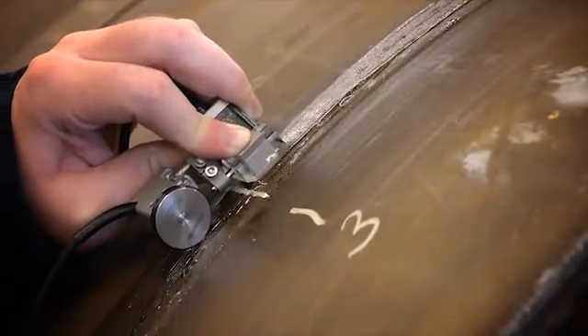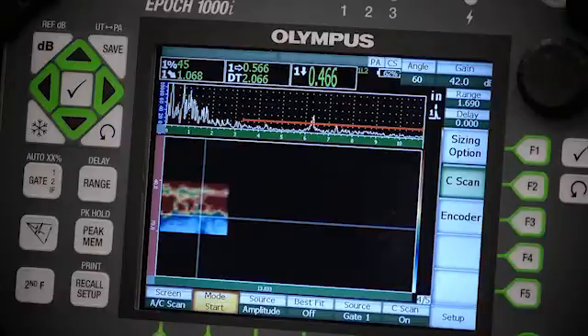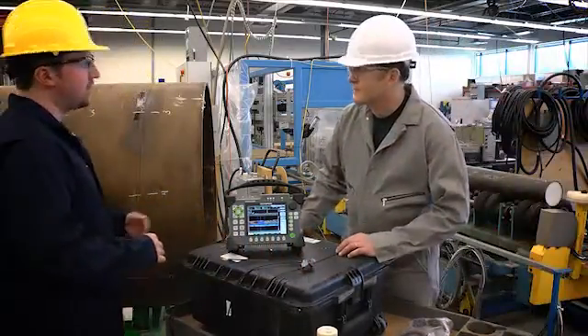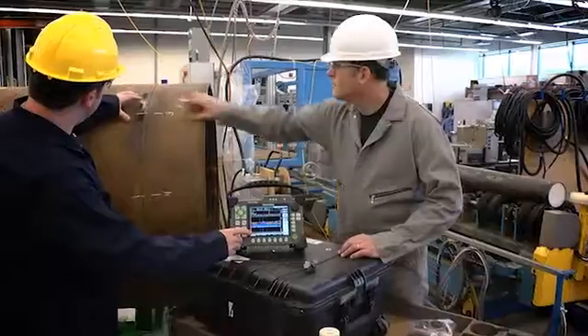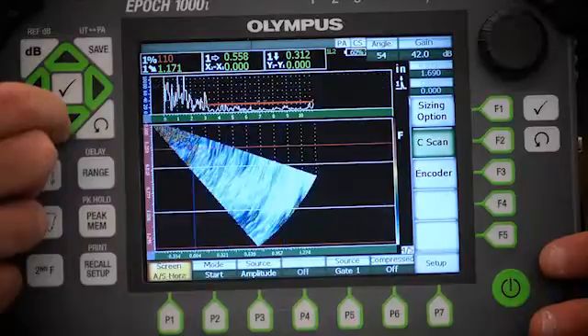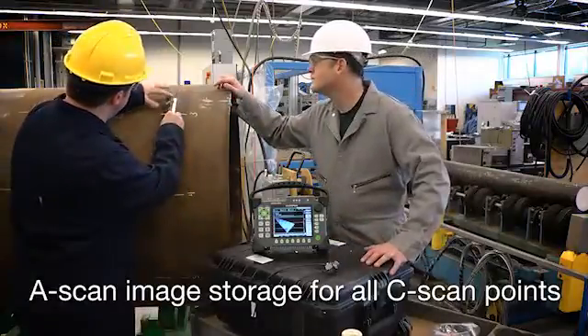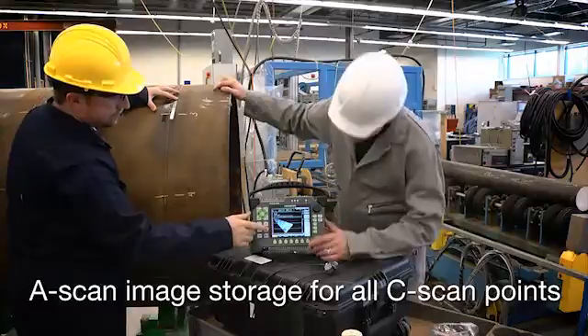Encoded C-SCANs allow you to quickly accumulate data from a large inspection area for fast visual review of areas that need additional evaluation. During C-SCAN acquisition, you can view the live A-SCAN on screen along with the C-SCAN. Compressed A-SCAN images can be saved for all C-SCAN points, allowing review of single scan points as well as recreation of the sectorial or linear scan from the selected position of the scan.